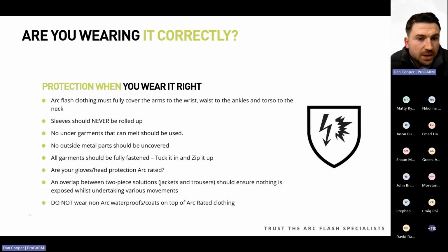Are your gloves and head protection arc rated as well? Not everywhere, but a lot of companies - people may wear just the arc flash coveralls, t-shirts, and trousers, but their hands and face are probably closest to the work because of the nature of it, and they're unprotected, not wearing arc gloves or arc head protection with visors.